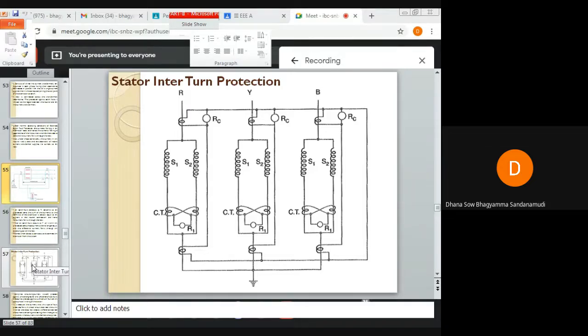So we have already seen the merz-price circulating current protection scheme. In that, we have already discussed that the circulating merz-price protection scheme can be used for protecting the generator windings or alternator windings against phase-to-phase and phase-to-earth faults. But it is observed that this merz-price protection cannot protect the alternator against interturn faults in the same phase winding of the stator.